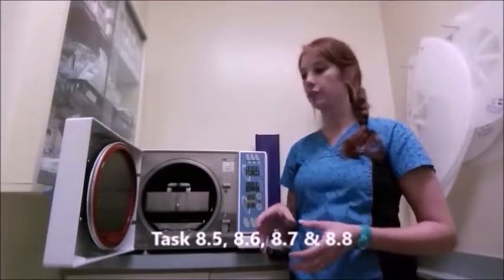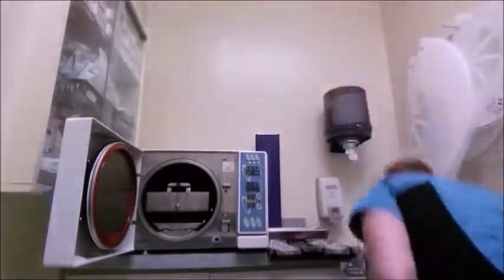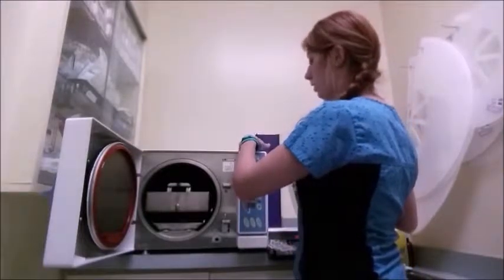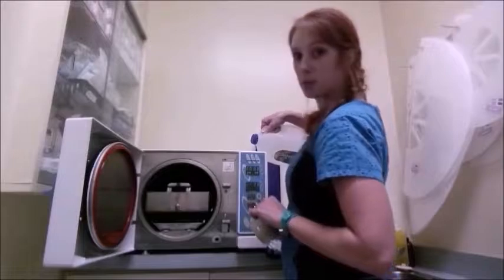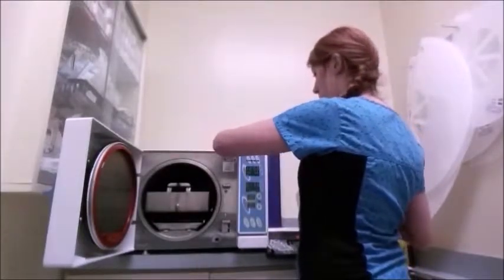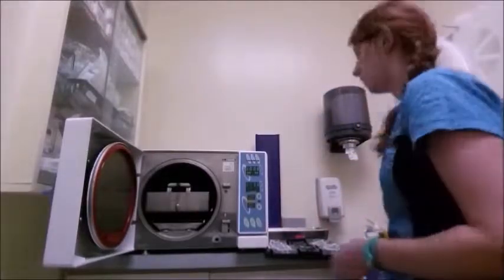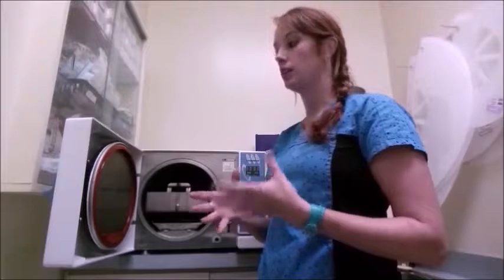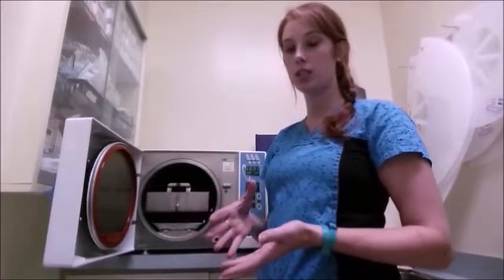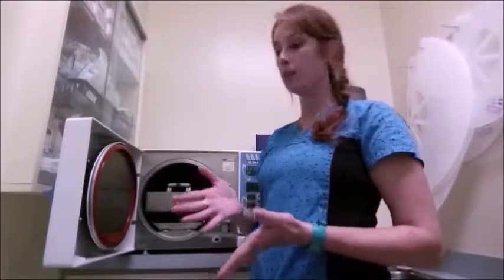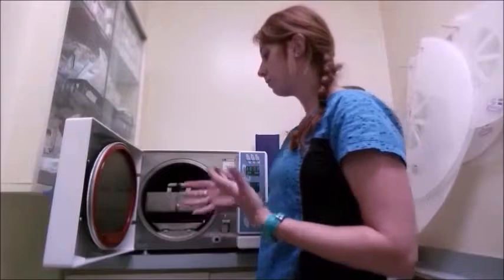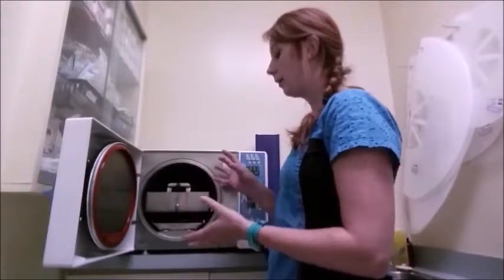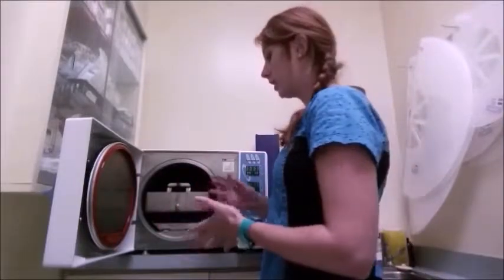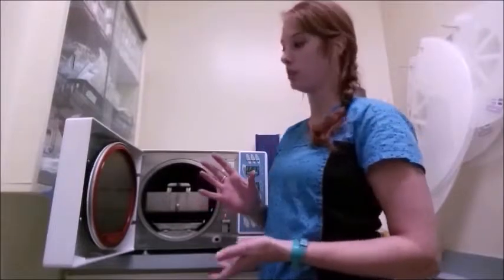Our autoclave is a gravity air displacement sterilizer. The way this unit functions is that we place distilled water into our reservoir fill, which happens to be on the top of our unit, up to a certain fill point. The water is then converted into steam, which pushes the air out of the unit. Once that steam reaches a certain temperature, it needs to be 121 degrees Celsius at 115 kPa, the cycle will then process for about 30 minutes to ensure proper sterility of our packs. The steam will then condense and turn back into water. So that is how the sterilization process works for one of these units.